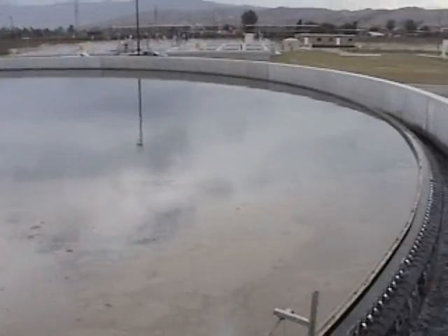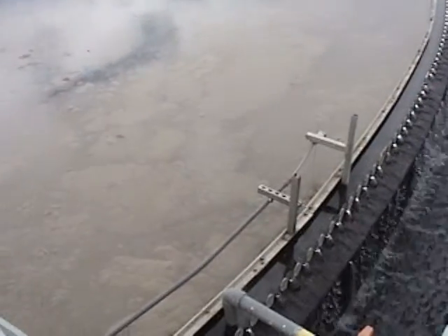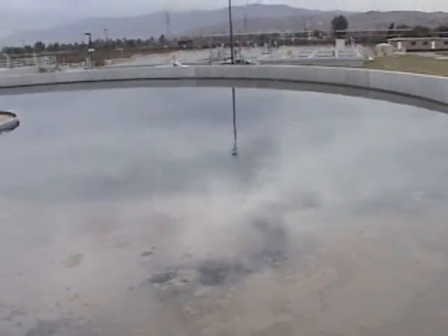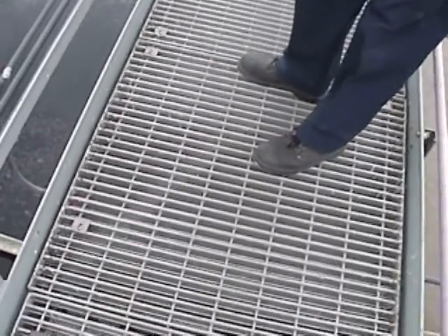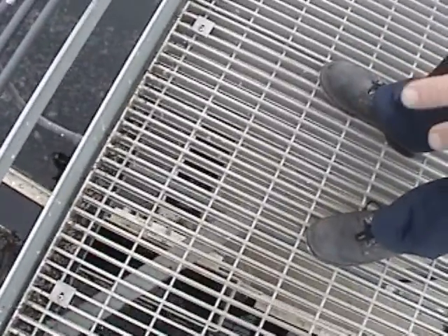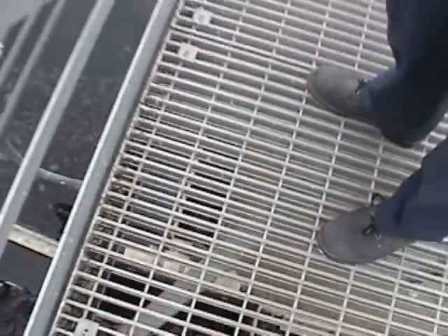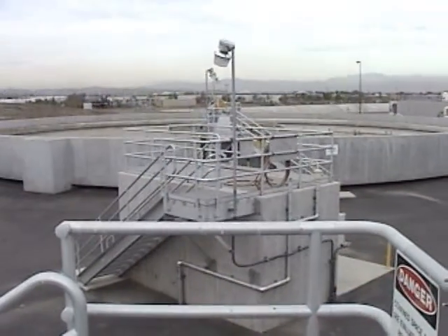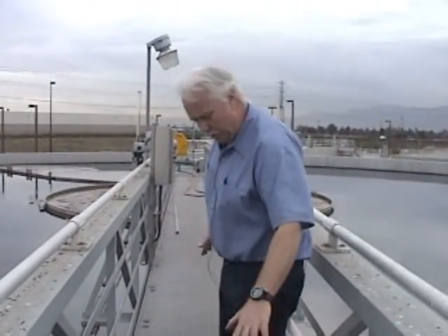If you start a blower up and this air compressor isn't running, the pneumatic valves up on the aeration basin won't open. The blower will still run, but you won't be pumping any air out there. Right now, this isn't too bad. But if this tank were covered with foam, and you looked down into this trough right here and it was full of foam, you would know that there's a problem. You're not pumping with the scum well, the scum pumps over there. And I'll show you something else too along here, this is what they call a ducking skimmer.